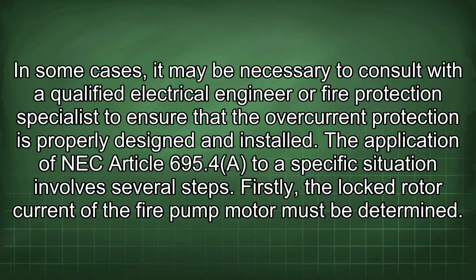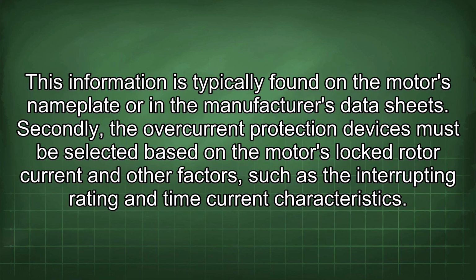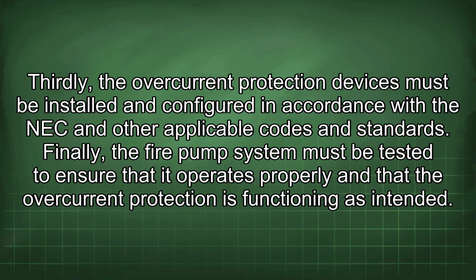The application of NEC Article 695.4 to a specific situation involves several steps. Firstly, the locked rotor current of the fire pump motor must be determined. This information is typically found in the motor's nameplate or in the manufacturer's data sheets. Secondly, the overcurrent protection devices must be selected based on the motor's locked rotor current and other factors such as the interrupting rating and time current characteristics. Thirdly, the overcurrent protection devices must be installed and configured in accordance with the NEC and other applicable codes and standards.